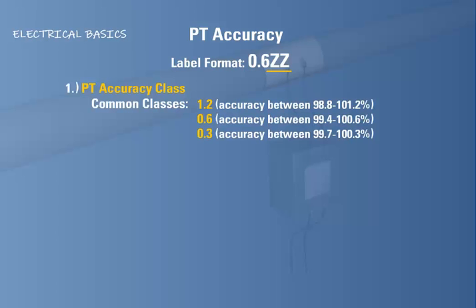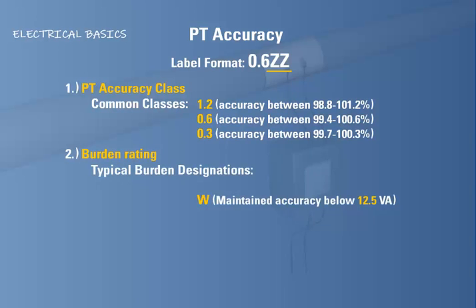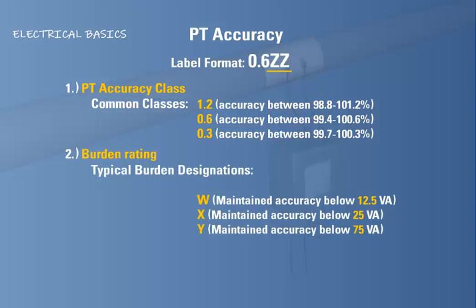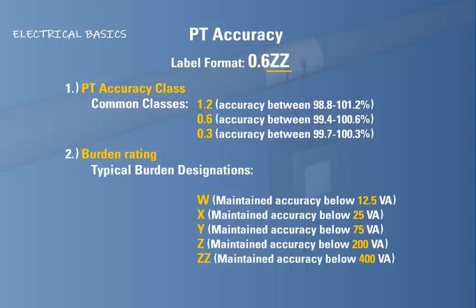The next character in the label is a letter designating the burden rating. The typical burden designations are as follows: the W rating indicates the PT will operate accurately as long as the burden doesn't exceed 12.5 volt amperes; the X rating, 25 volt amperes; the Y rating, 75 volt amperes; the Z rating, 200 volt amperes; and the ZZ rating, 400 volt amperes. If at any time the burden exceeds the PT's rating, the accuracy classification will be compromised.